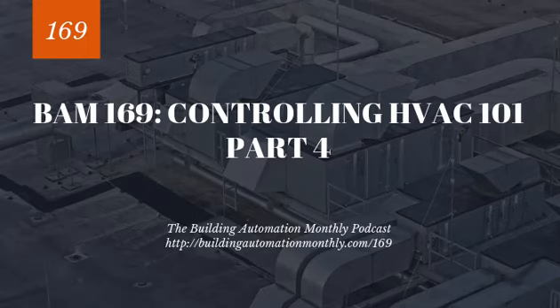Now, as far as fuel goes, typically you're going to have very little to do with fuel except for maybe adjusting fire rate via a resistor or 0 to 10 or 4 to 20 signal, sometimes via MSTP or BACnet signal, which, by the way, I really recommend when you're controlling boilers that you hardwire things. It's just much easier to troubleshoot than having a Modbus or a BACnet interface to the boiler.